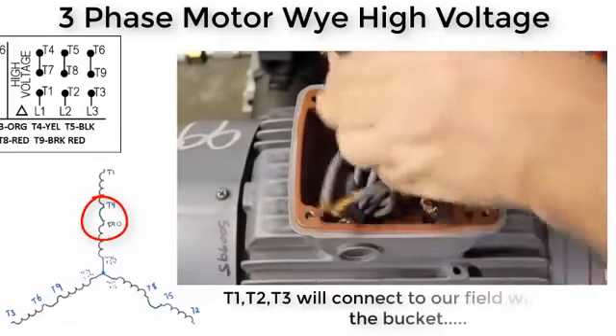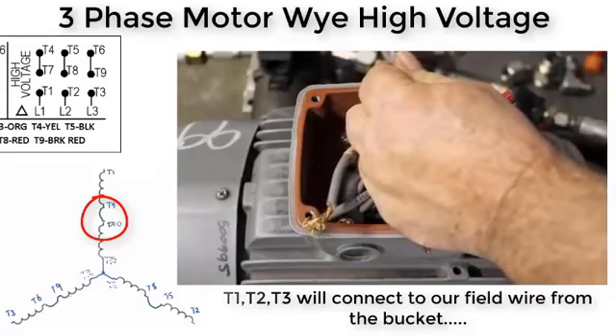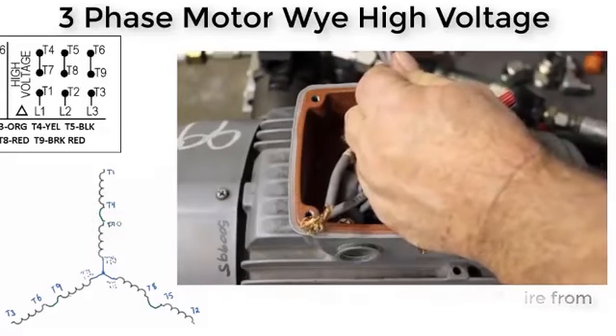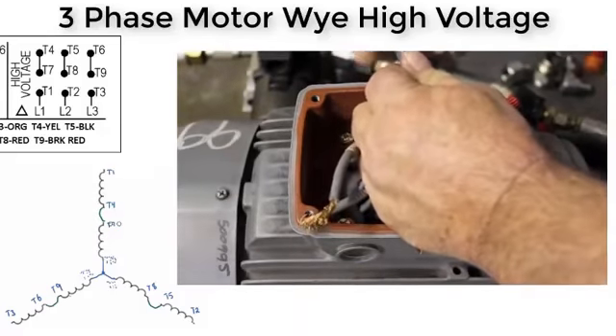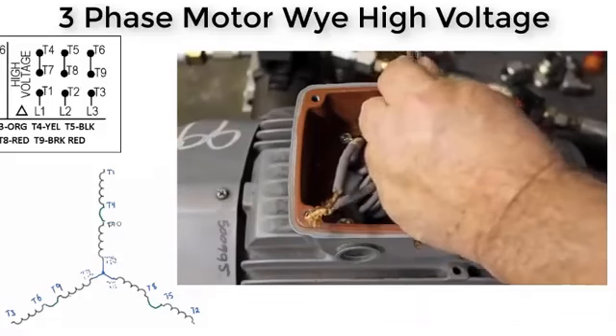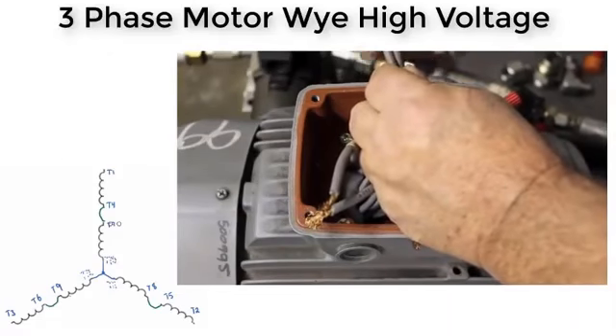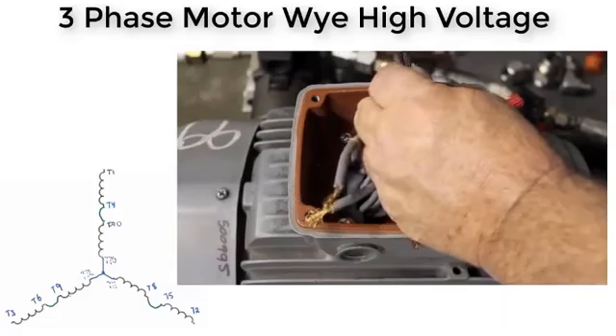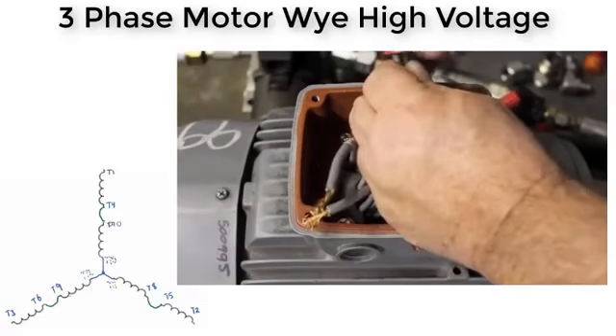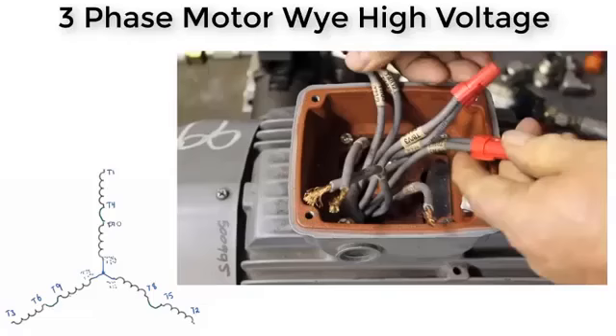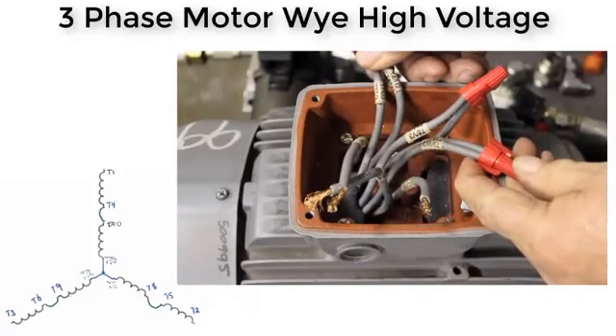Now you have 1, 2, and 3 go to L1, L2, and L3. After you've done that, if your motor's going in the wrong direction for the pump, reverse any 2 of the 3 leads, L1, L2, or L3. And that's 9-wire 460 wiring.